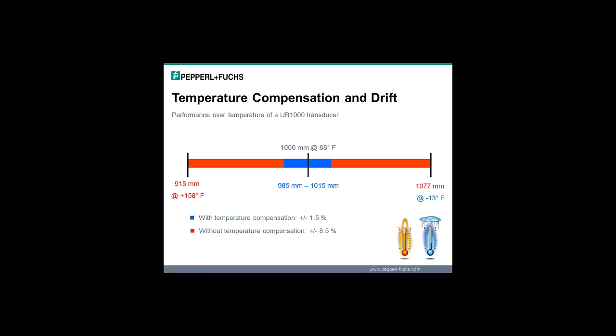Here's a simple graphic that shows the temperature drift and the effects of having or not having temperature compensation. And this would be for a UB1000 model where the target would be at 1,000 millimeters. You can see at 1,000 millimeters and 68 degrees Fahrenheit, you get a 1,000 millimeter output. So the sensor knows exactly where the target's at. With the temperature compensation, you can still have a variance of about plus or minus 1.5%. So it could go down to 985, could go up to 1,015, and that's more a component of the lag because the temperature compensation element is inside the sensor. So the outside temperature may change a little bit, and then the response of the sensor for compensating for that may lag a little bit just because it's kind of buried inside the sensor.